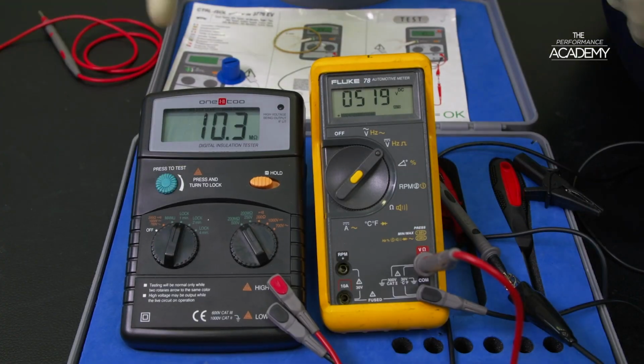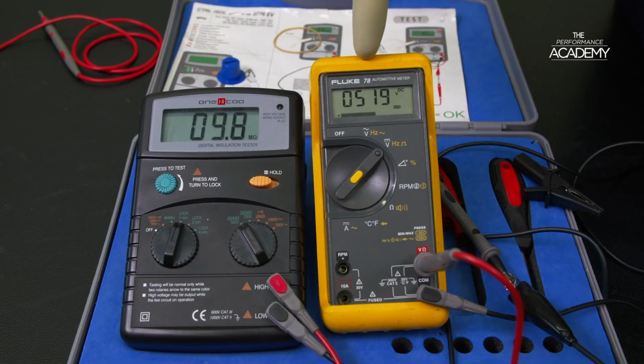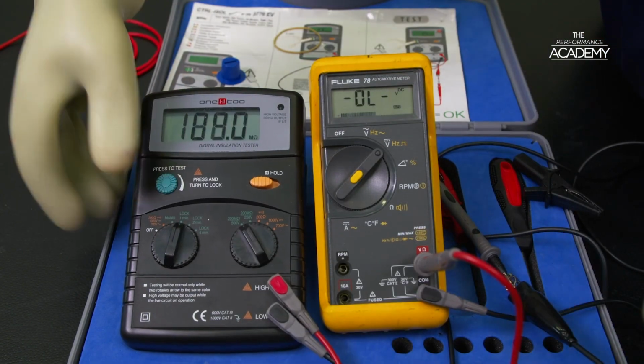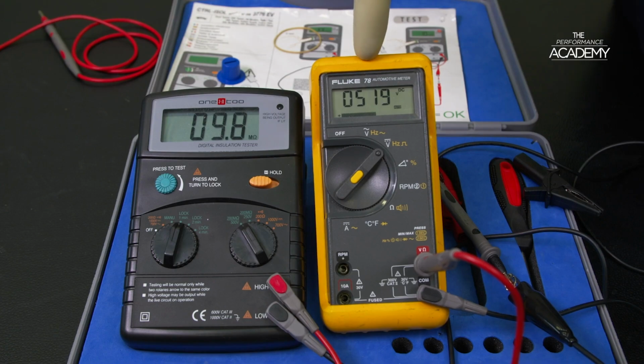Next, we need to check the test voltage output of the insulation tester to ensure the output is 500 volts or more. For this, we use an additional multimeter, which also enables us to check the insulation tester is reading correctly. Standard multimeters have an internal resistance for voltage testing of approximately 10 to 11 megaohms. So, with the test leads connected to our multimeter, we not only check the output is 500 volts or above, but looking at the insulation tester display, we should be able to read the multimeter internal resistance of between 10 to 11 megaohms. Remember, the same test and checks must be applied after completing any measurement testing to ensure the insulation tester was emitting 500 volts throughout the duration of the test.